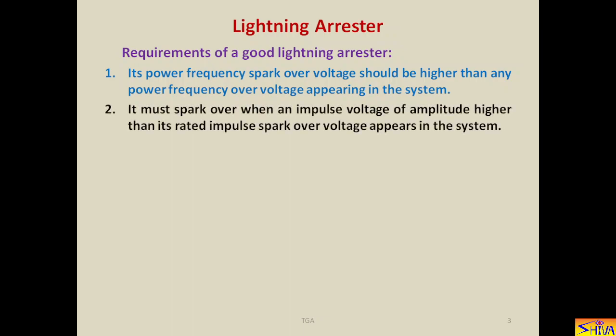Next requirement is it must spark over when an impulse voltage of amplitude higher than its rated impulse spark over voltage appears in the system. Now as per Indian standard, the impulse voltage is characterized by a 1.2 by 50 microsecond wave. 1.2 microsecond is the rise time and 50 microsecond is the tail time, and its peak value we denote by Vp, that is in kV. So the second requirement from the lightning arrestor is that it must spark over when an impulse voltage of amplitude higher than its rated impulse spark over voltage appears in the system. So the second rating for which the lightning arrestor is to be tested is impulse spark over voltage.